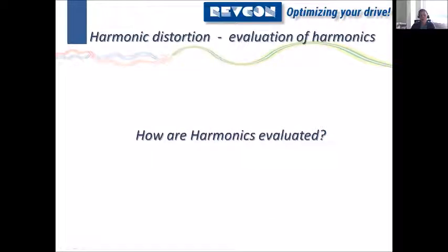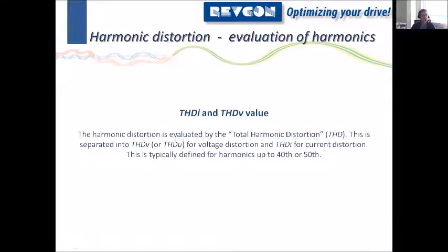Okay, so how are harmonics evaluated? I'm quite sure you have heard these values before: THDI and THDV values. These are the evaluation numbers to expect certain results. For example, THD means total harmonic distortion and is defined typically up to the 40th or 50th harmonic. And this is made for current and for voltage.